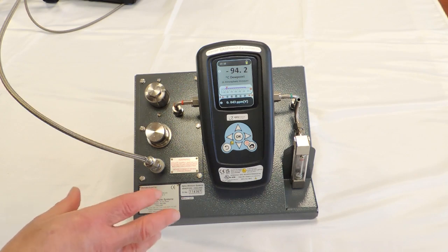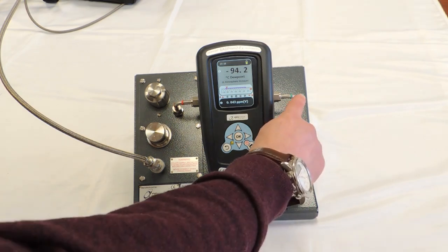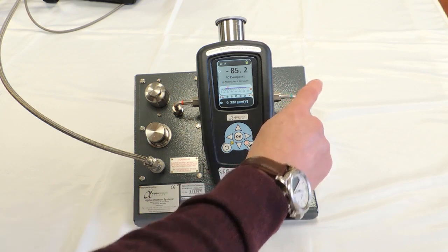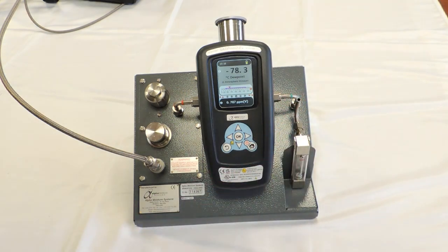We've now purged through the PSS and the instrument for a few minutes. We then raise the head of the instrument by blocking the outlet like this. Release and you'll notice that the dew point responds very quickly and rises until it reaches equilibrium with the sample gas dew point.